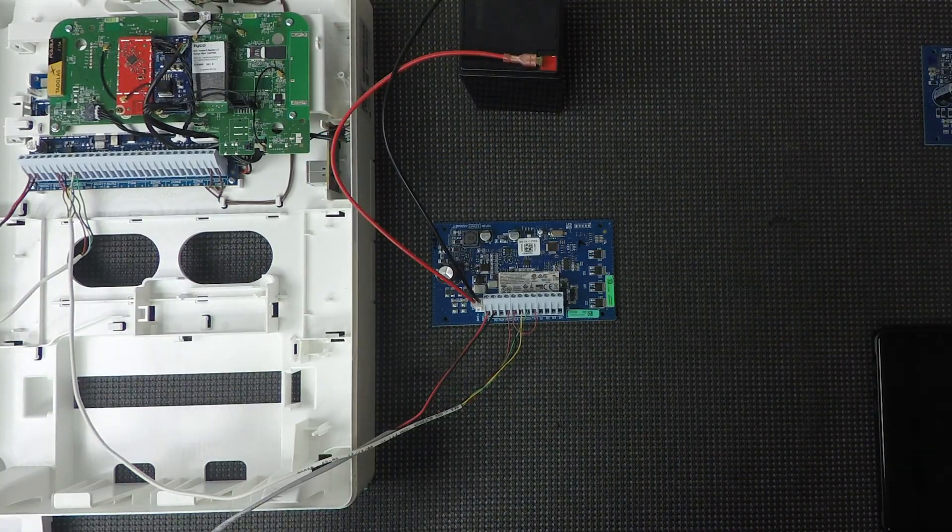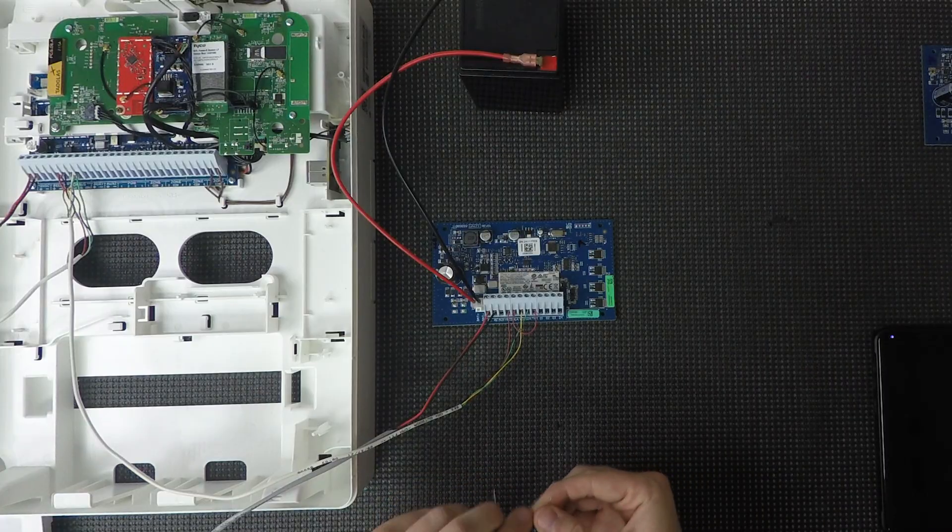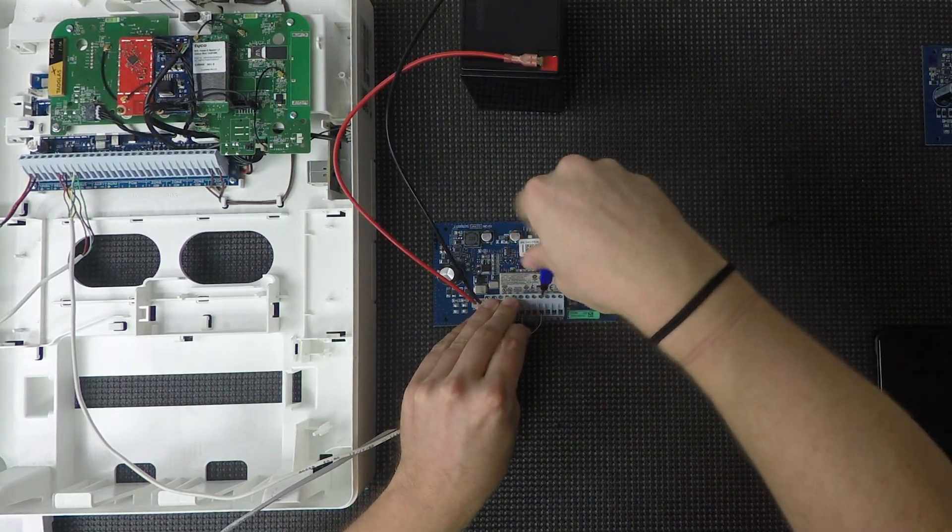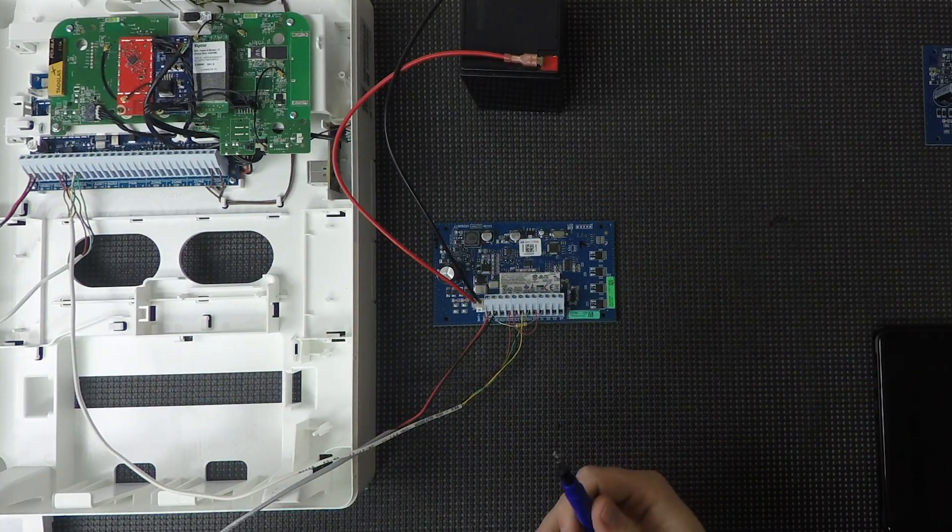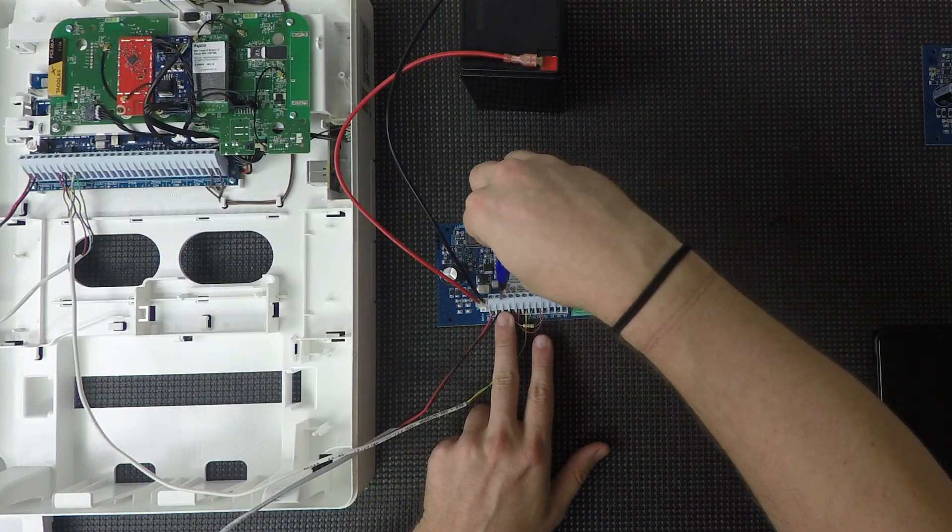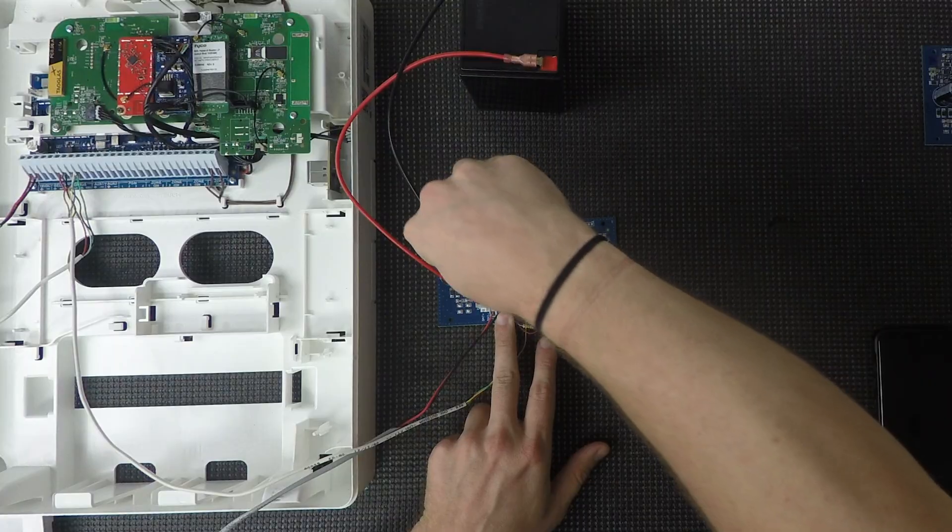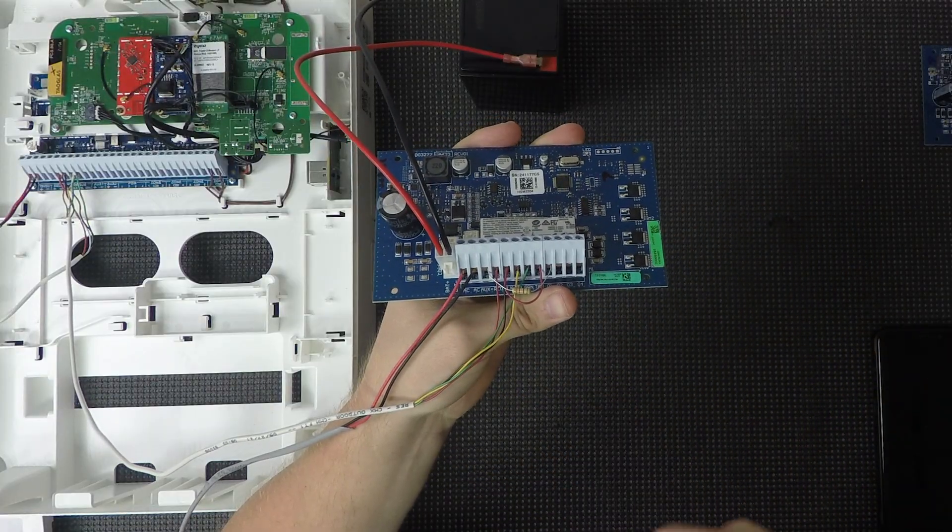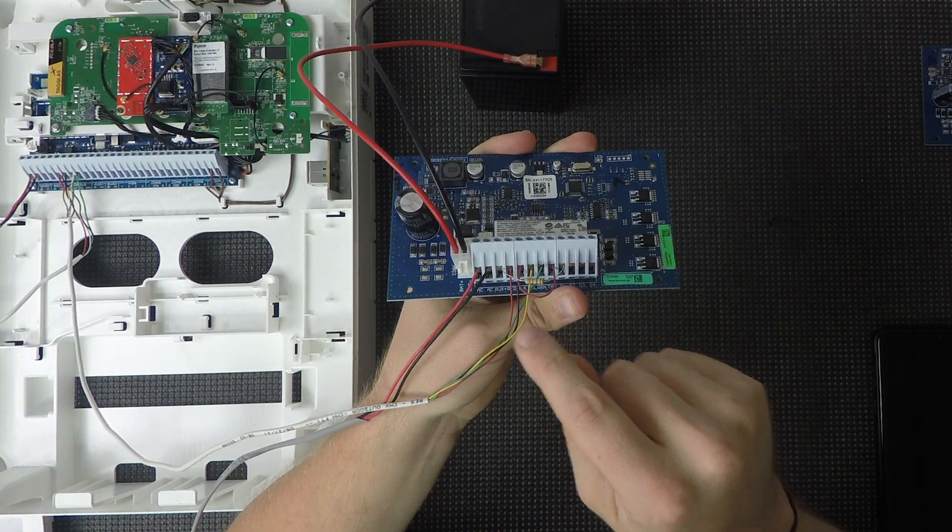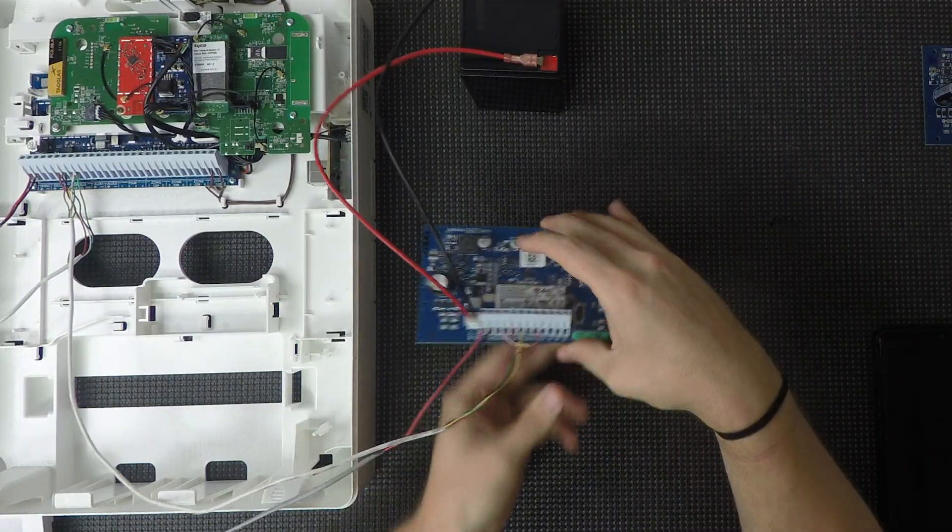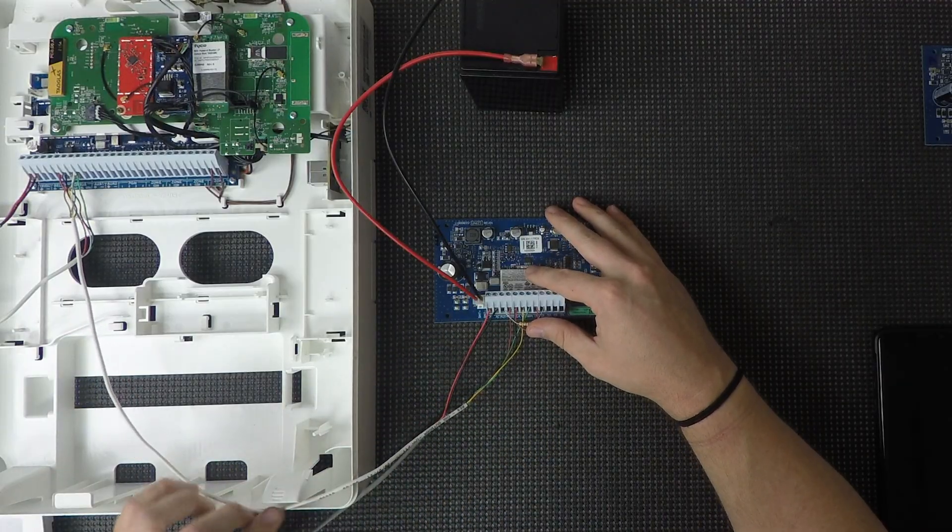Now one other thing you can do preemptively is take a resistor. It just needs to be 1K or higher. So this is a 5.6K, it's a little bit high, but it serves the same purpose, and we're going to connect that to O1 and aux plus, and all that's going to do is basically tell O1, since it is designed as a secondary bell circuit, that there is enough resistance, and it does not need to throw a fit about it. If we booted this up, it would basically show a bell circuit trouble on our power supply module. So, it gets a little stacked here, especially once you start adding devices, but this is what your basic setup for the wiring is going to look like. You're going to have your two AC wires on the left, your resistor connected to aux plus and O1, your tamper jumper connected from black to tam, and then you'll have your four core bus wires, and then of course your battery connection as well. So, bare minimum, this is what you should do when you first connect this module to your system.